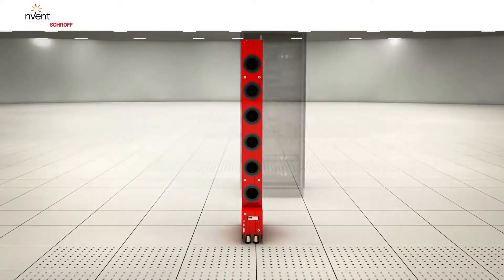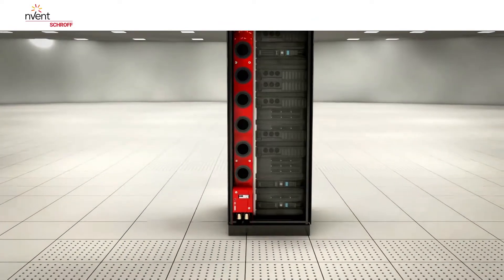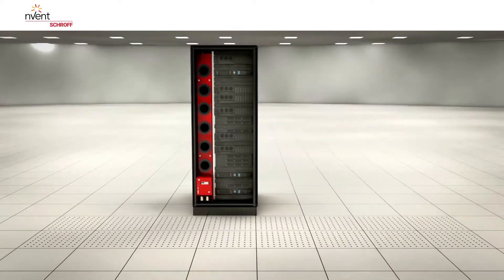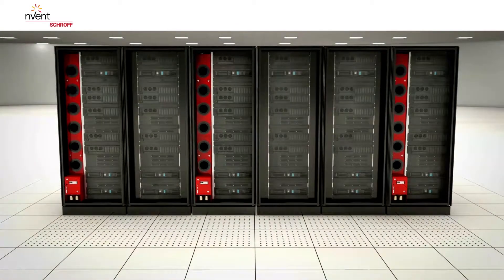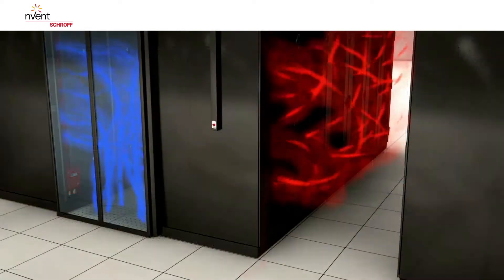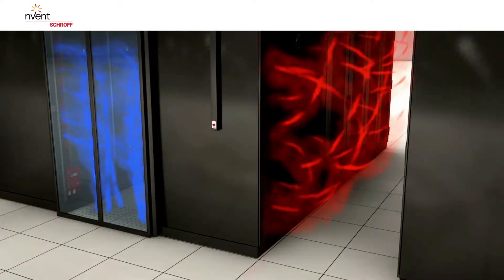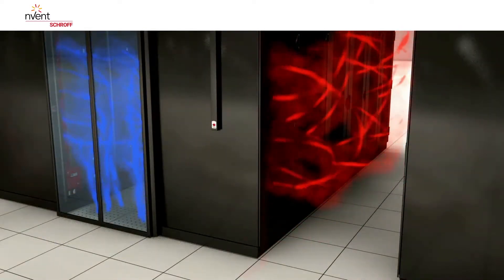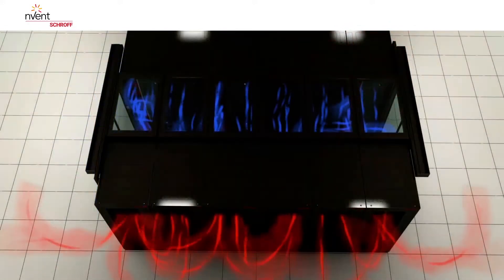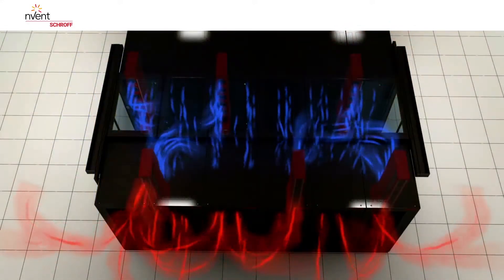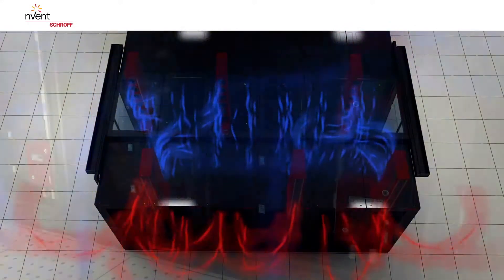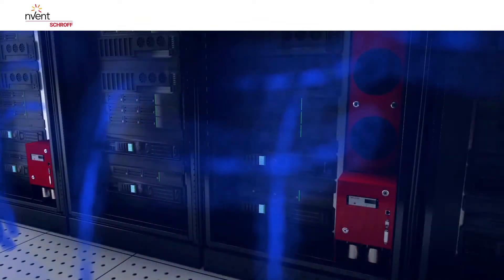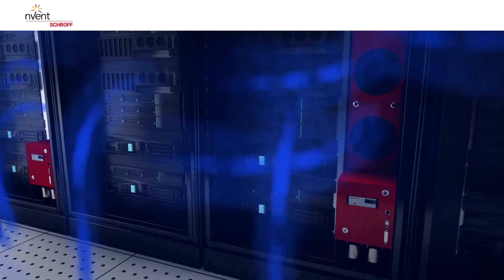The entire thermal load of the data center is distributed evenly onto air-water heat exchangers within the individual server cabinets. These draw the warm exhaust air from the rear of the hardware and out of the server room and cool it in the integrated cooling unit to a temperature set by the user. The cooled air is then blown in from the front via the redundant built-in fans in the closed cold aisle.